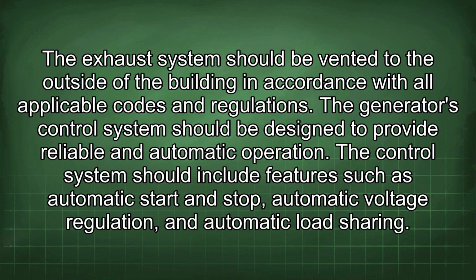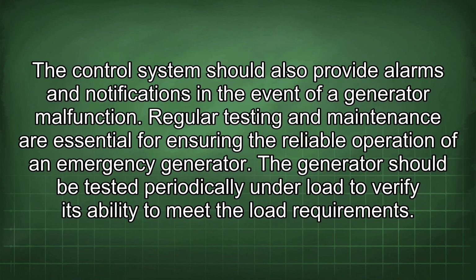The generator's control system should be designed to provide reliable and automatic operation. The control system should include features such as automatic start and stop, automatic voltage regulation, and automatic load sharing. The control system should also provide alarms and notifications in the event of a generator malfunction. Regular testing and maintenance are essential for ensuring the reliable operation of an emergency generator. The generator should be tested periodically and allowed to run under load to verify its ability to meet the load requirements.